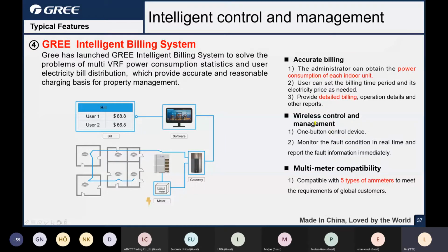And for the control and the management, that's the one button control. The billing system is not only for billing calculation, you can also use it as a management platform. You can control all of the indoor units with just one click, and monitor the fault condition of every indoor unit running. If there is a fault, the computer display will show a warning to remind you and report to you to do the troubleshooting.